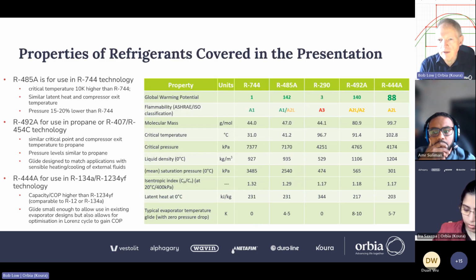So I'm not going to go through every line in this table, but I put it in the slides on the assumption that afterwards, people that want to get a copy of the slides and the numbers are in there for reference. Really, we're talking 3 pressure levels. We're talking about 485A being the similar pressure level to CO2. And we've been testing it and basically dropped into CO2 technology. Unlike CO2, that's got a critical temperature over 40 Celsius, which means it can basically run more efficiently in a much broader ambient temperature range than CO2 can.